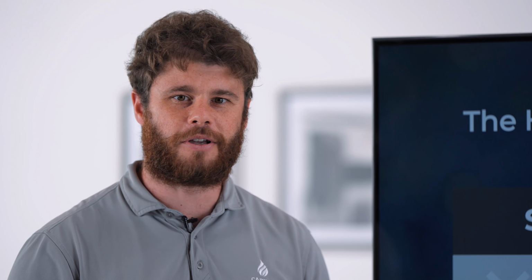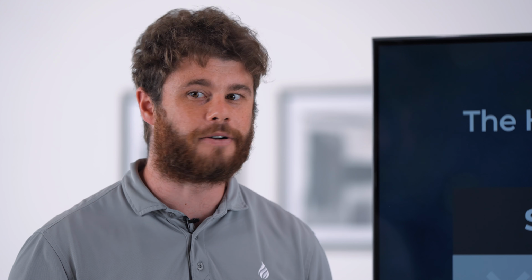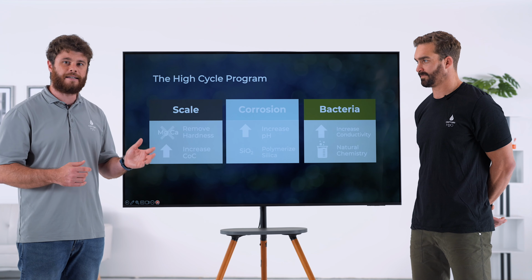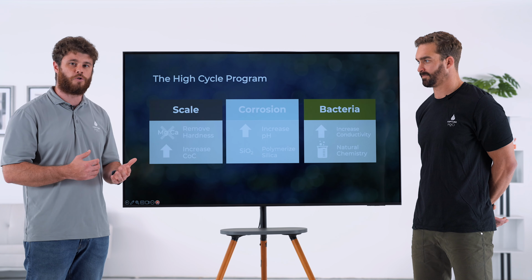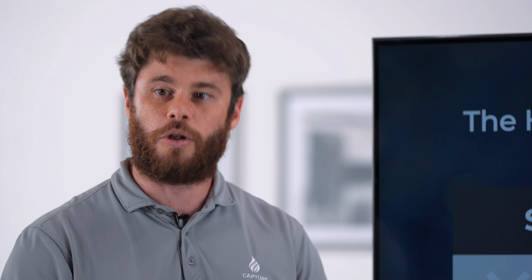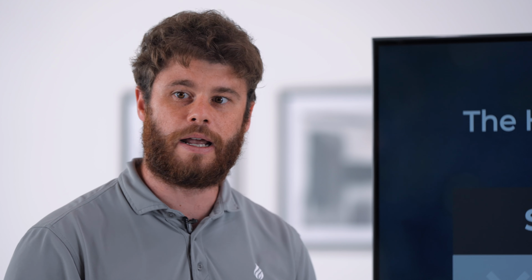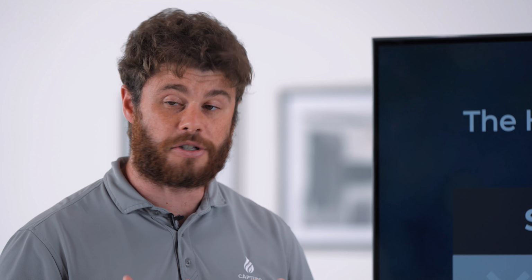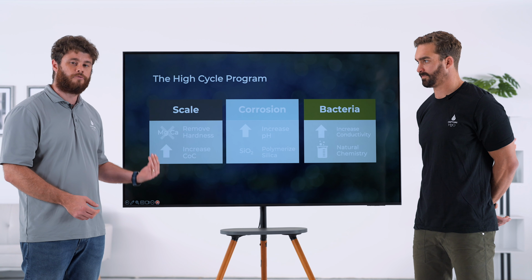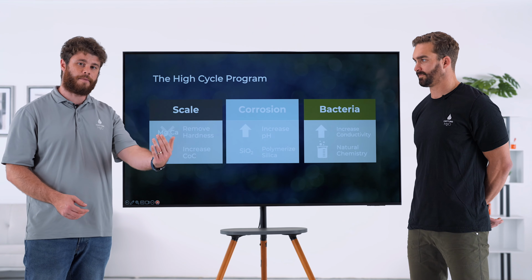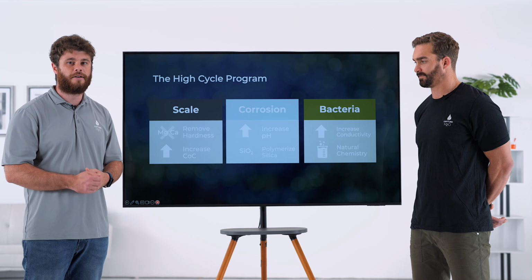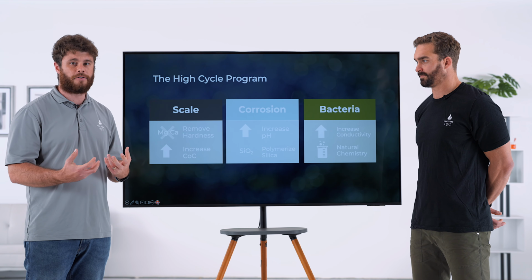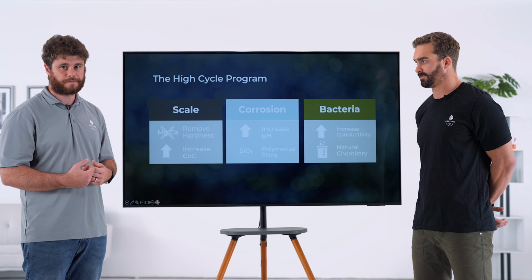Now, we're not coming at you with some crazy science here. Silica has been used for many decades in various systems as a corrosion control mechanism: closed-loop systems, radiators, car batteries. It's just not often used in cooling towers because of the hardness in the water. When we pre-treat the water, remove the hardness, and can achieve a high pH and high silica environment, we're able to utilize the silica in the water to control for corrosion.